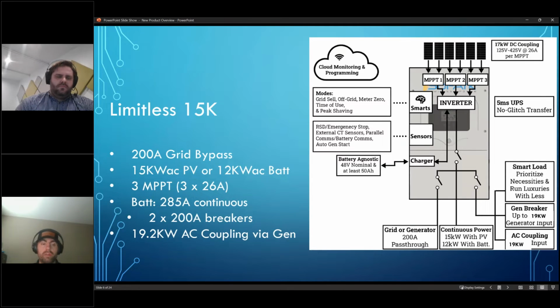One thing I want to point out is this also has up to 100 amps of peak performance, so over 24 kilowatts of peak output. That really helps with higher inductive loads—air conditioners, pumps, things of that nature—that need that inrush to help power and get them going.